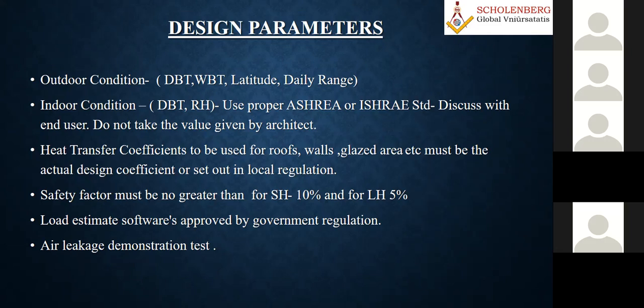Even here now, basically, when we use it, we normally take the same. For the sensible heat, normally we take 10%. For latent heat load, we take 5% only. And then duct loss and all the things, on average, we take 7.5%. So then, whatever software we are using should also be approved by the government regulation. This is also very, very important.